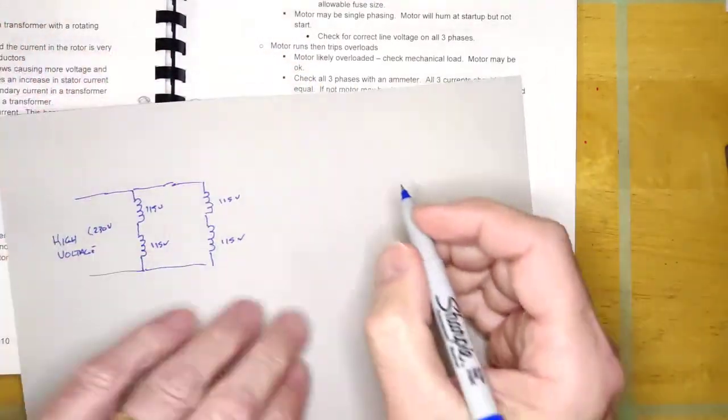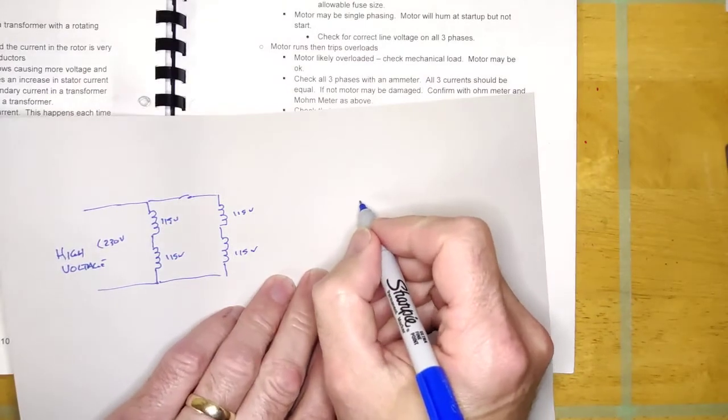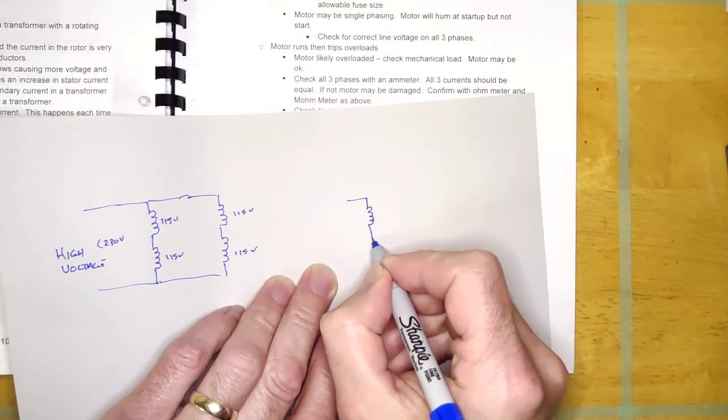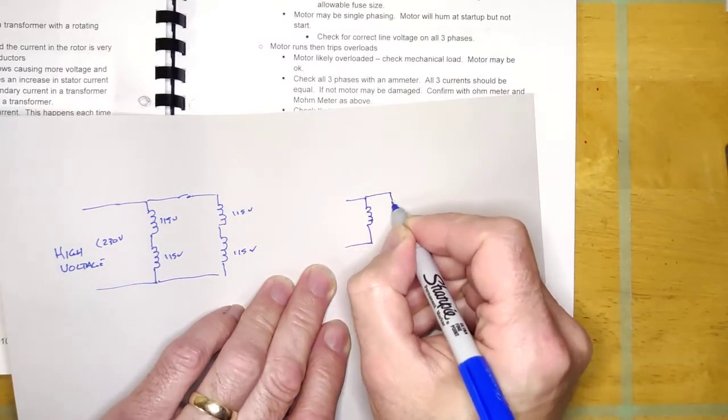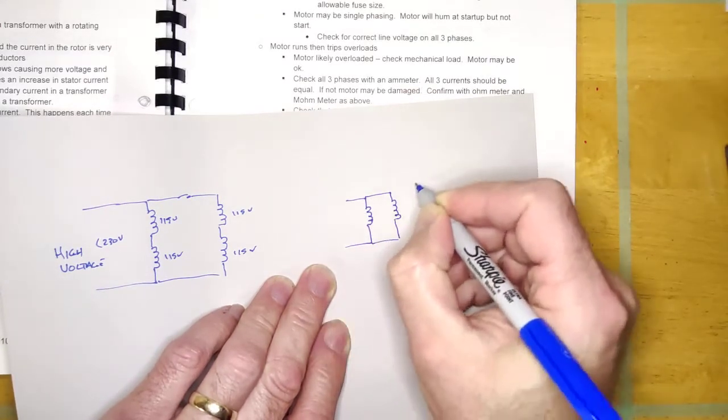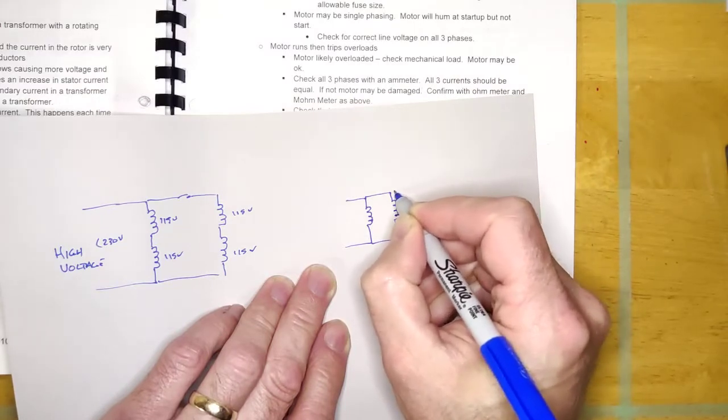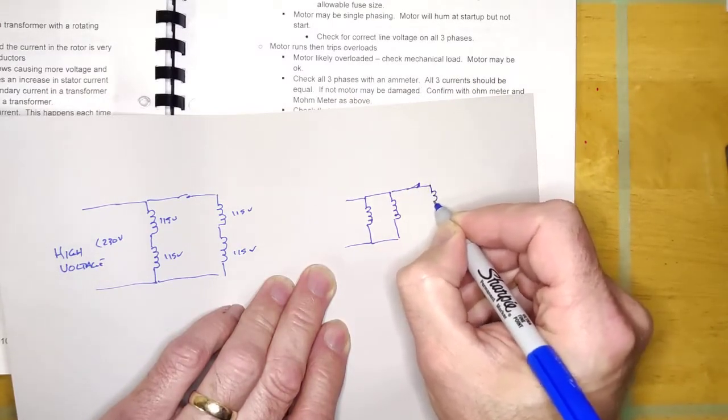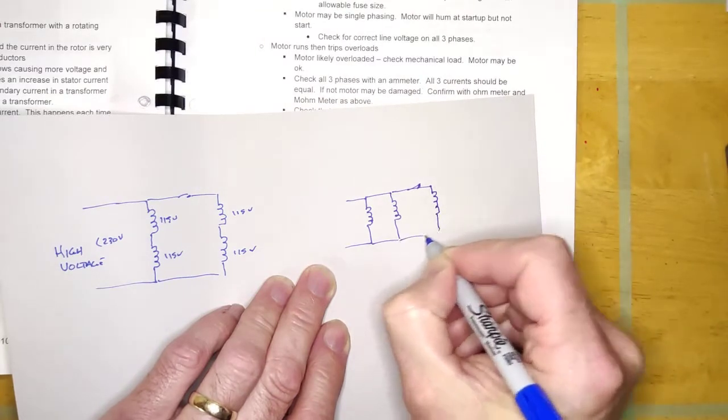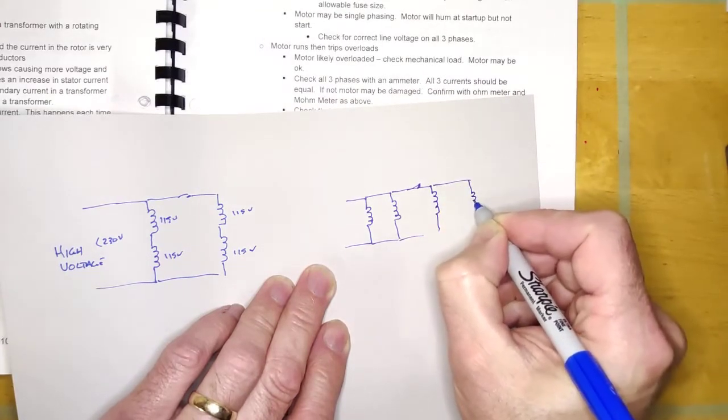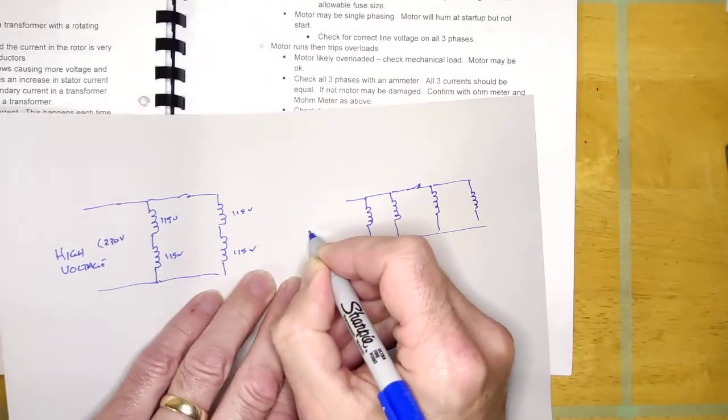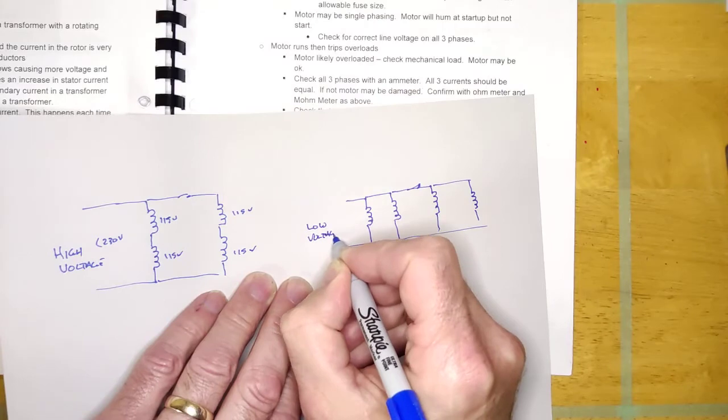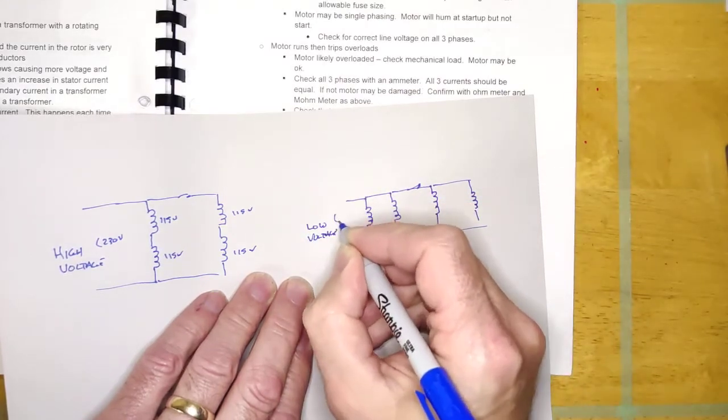And right now this thing would be wired high voltage. Because if it was high voltage, in other words, you had 230 volts from here to here, then this one would see 115 volts, and this one would see 115 volts, and this one would see 115 volts, and that's because they're wired in series, 230 volts.